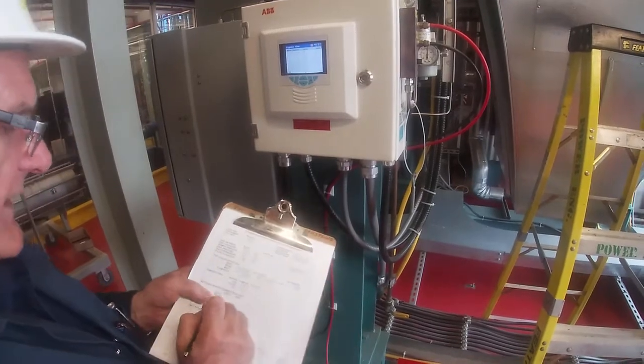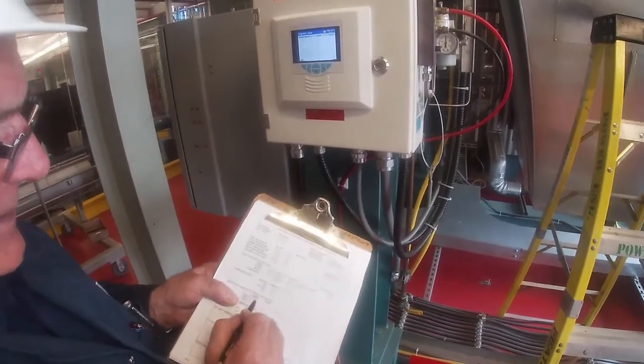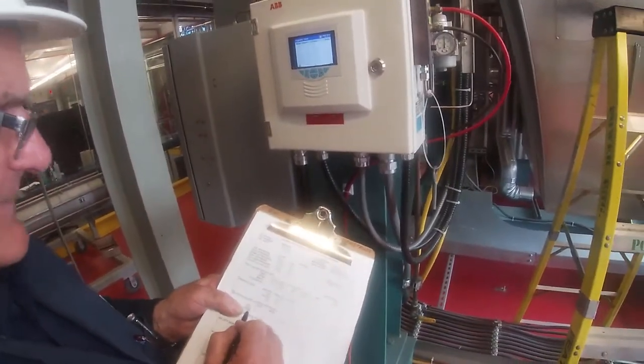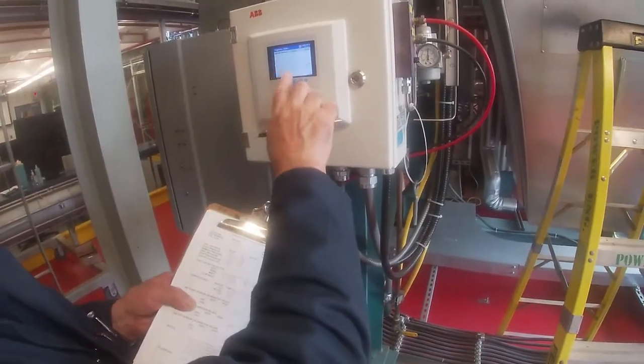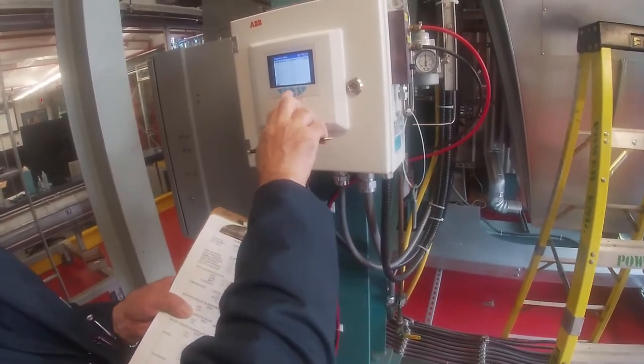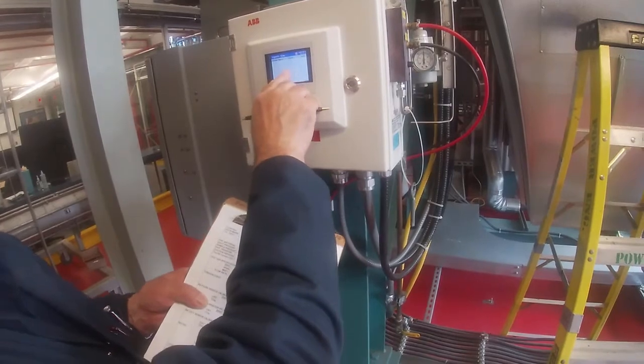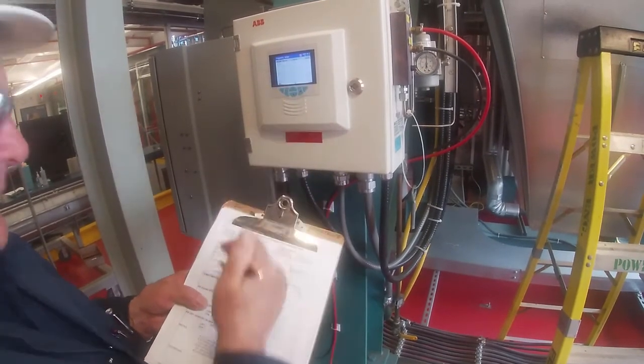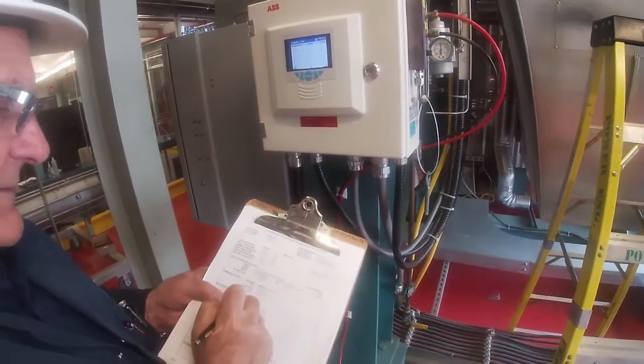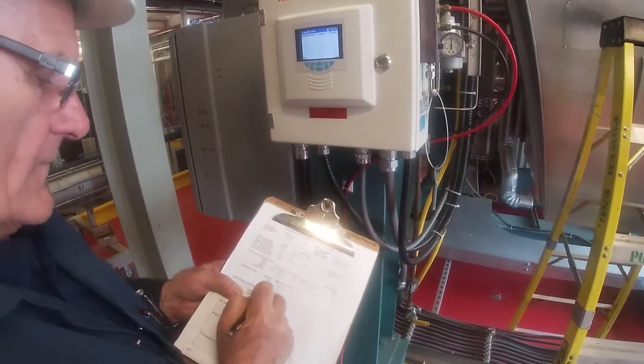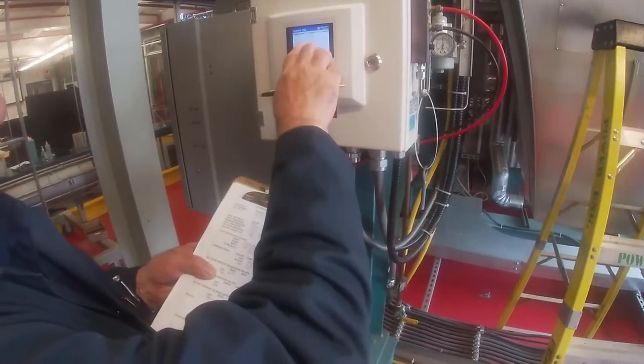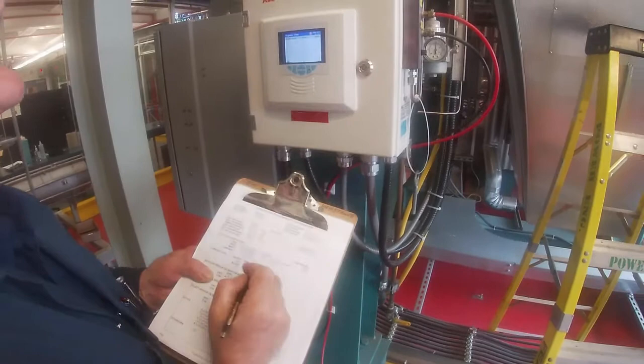We want to know what the as-found calibration values are, so zero and span for the oxygen. The next page will give me the oxygen sensor, and the zero is 63.4 millivolts, and the span is sitting at minus 3.8.